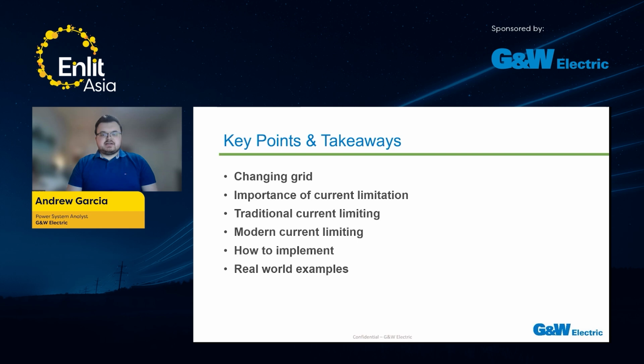So what are the key points and takeaways I would like you to take from this presentation? The grid is changing. There's an energy revolution: data centers, renewables, distributed energy resources, all the typical things the industry has been talking about the last couple of years. It's happening, and it's changing the grid in ways we anticipate and probably in ways we can't. As a result, there's going to be a much higher importance on current limitation, because as the grid changes, the available fault current is anticipated to go up as you plug in all this new generation via renewables and battery energy storage systems, and new load via data centers.